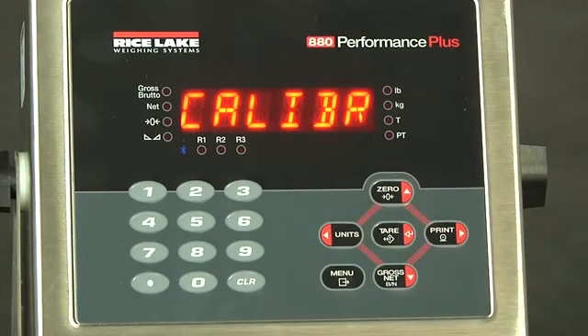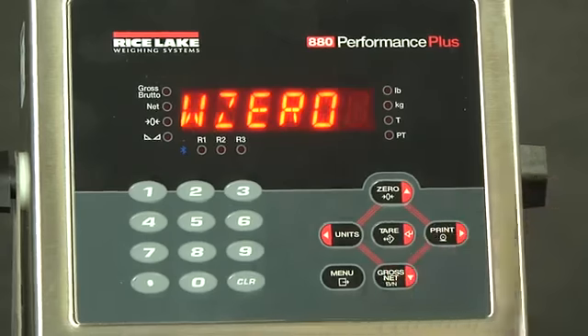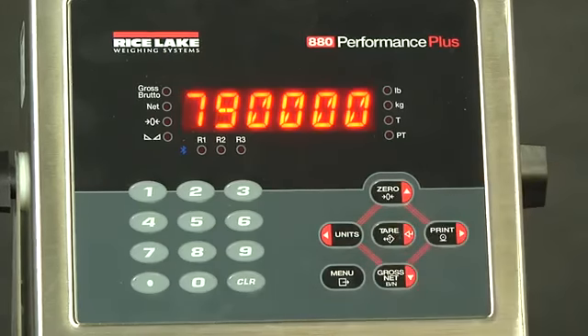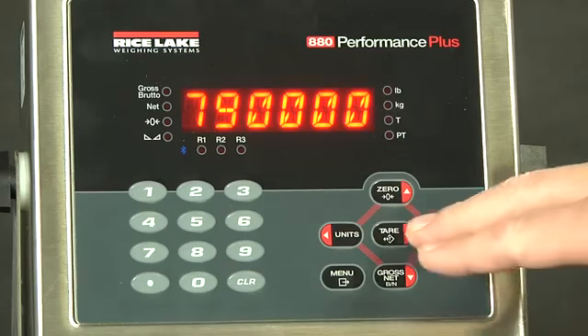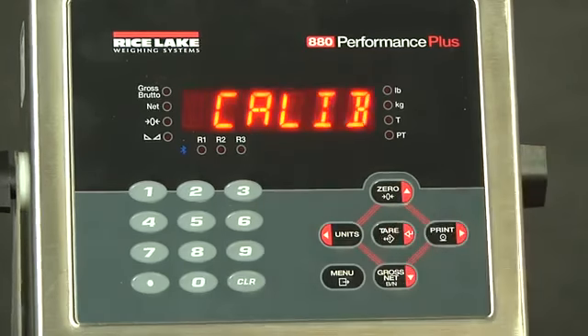Calibration is where you perform the W0 and W span of an object, which is a 2-point linear calibration. There are more available options which we will go into in other videos. As we drop down here, we have the W0. This is the point where, at the dead load of the scale, you want your 0 reference point to be. If we hit enter here, it will show us our current counts. This was the counts that was for the previous W0. If we hit enter now, it will go into calibration.